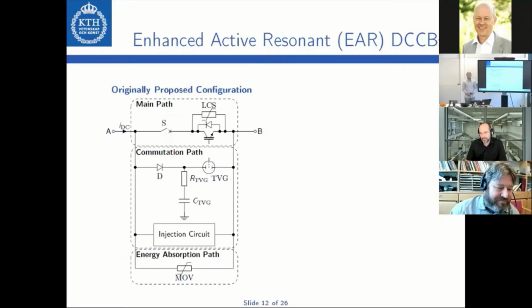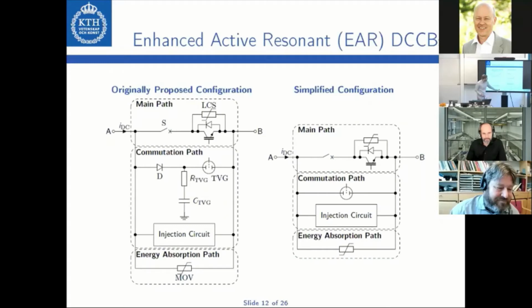I think I would try to avoid this question by saying that I've drawn this injection circuit on purpose in a general way, because the frequency limitation is heavily dependent on how the injection circuit is realized. For instance, this one here is compatible with basically all injection circuits. Then there are some types of injection circuits that build up the injection current successively with oscillations, and by doing this, the current is gradually ramped up to the interruption level. This means that the voltage and the current of the injection circuit are ideally suited to the current level, which reduces the dI/dt and dV/dt requirements. So, if I can give a concrete example, this is like the SCiBreak implementation.